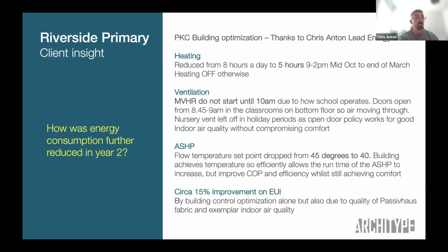The air source heat pumps were designed to 45 degrees. For people who don't know heat pumps, the lower the temperature you can get away with and the warmer it is outside, the more efficient it's going to be. So we lowered that down to 40 degrees and still hit the same set points. Our temperatures in the mornings are optimized, and our temperatures are high-limit during the day. It had no impact - we changed it without telling anybody, and nobody noticed, but the system works more efficiently.